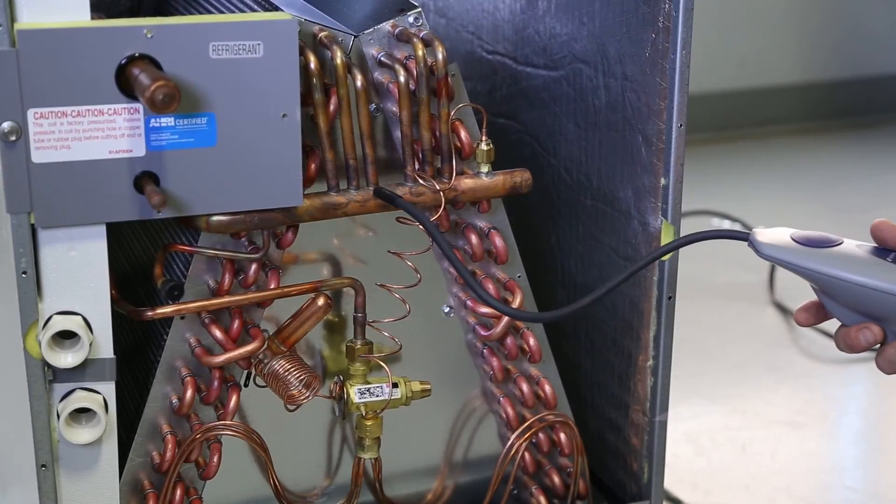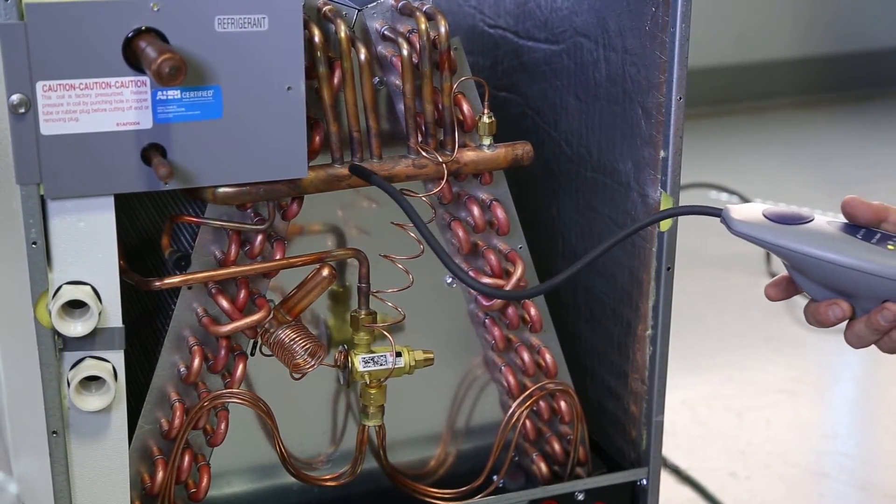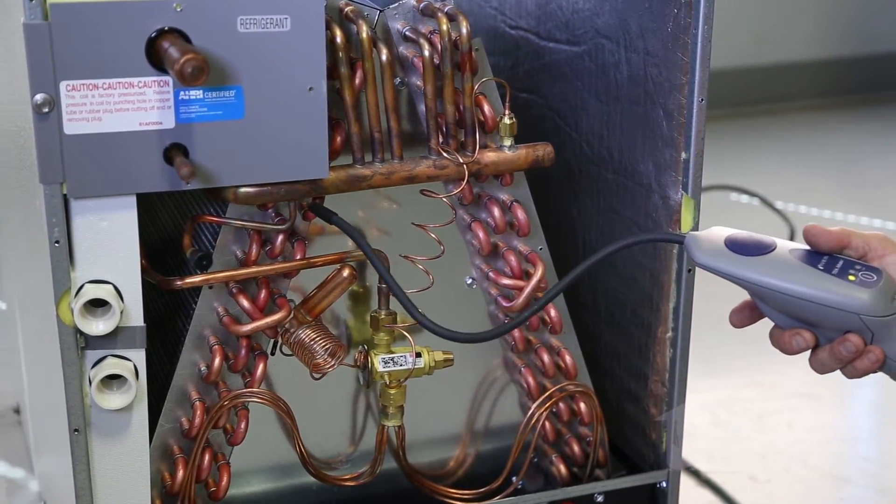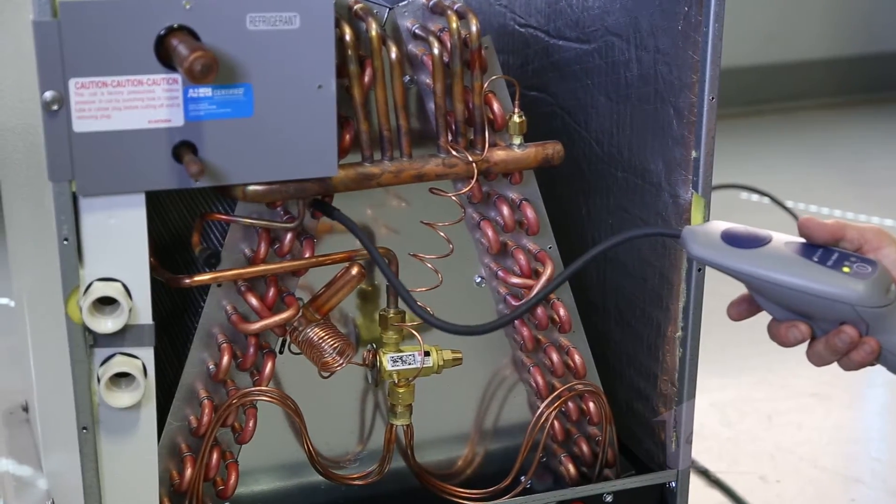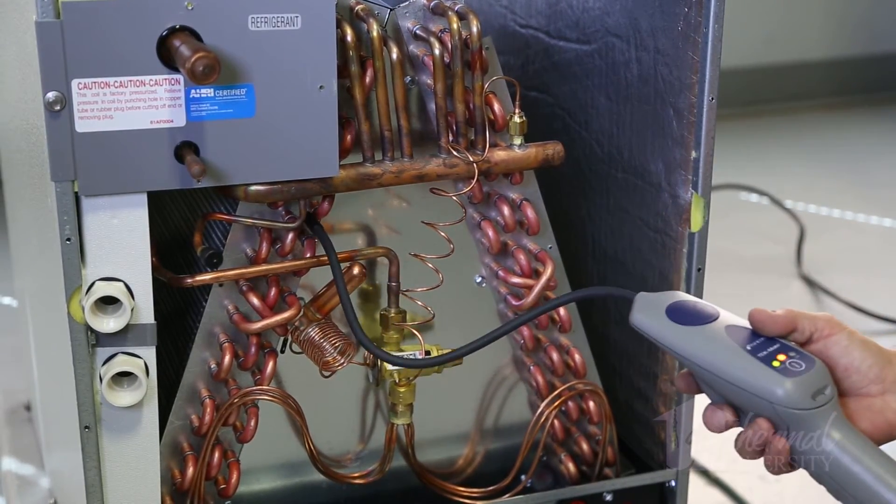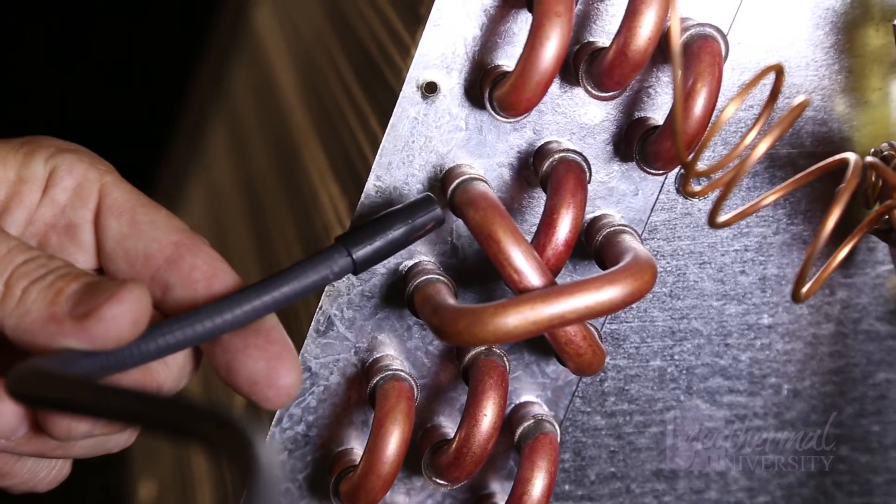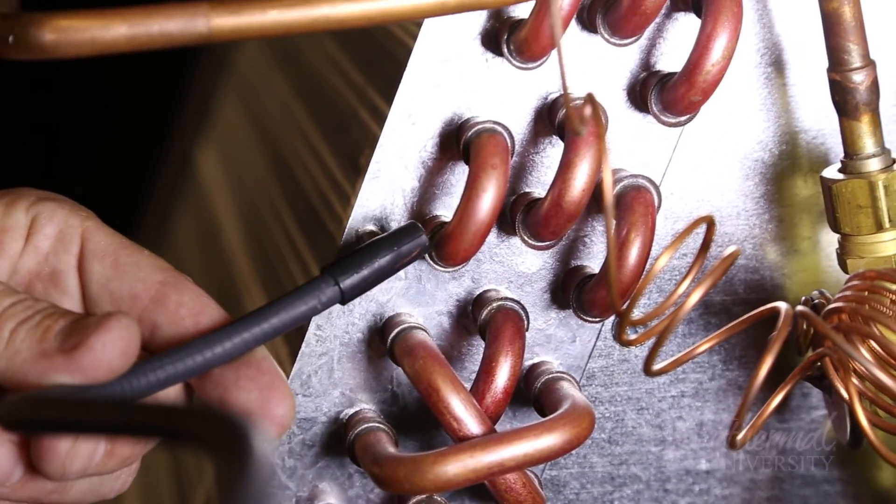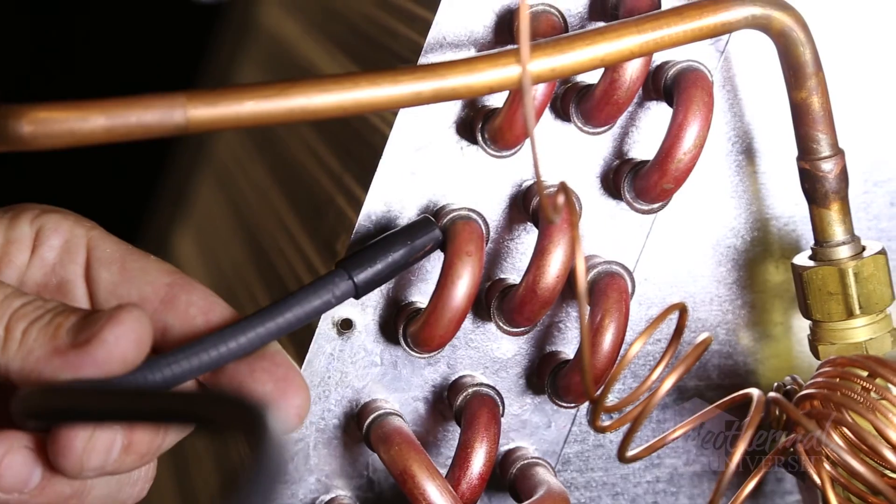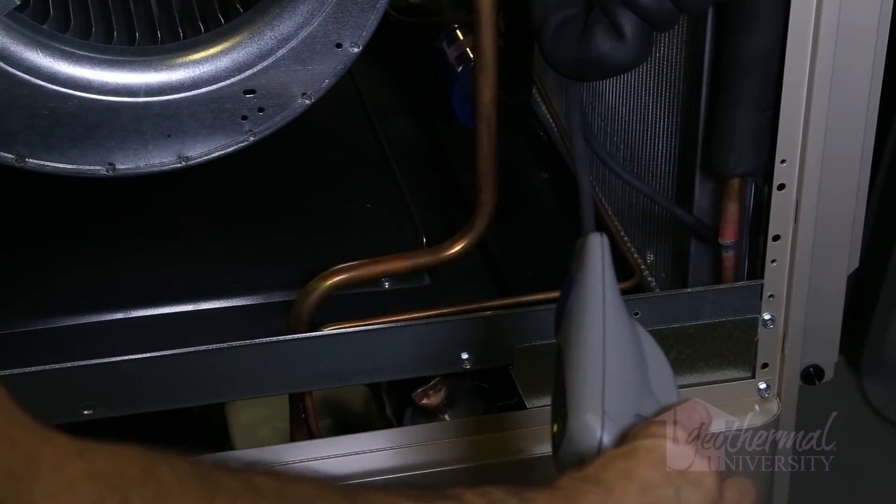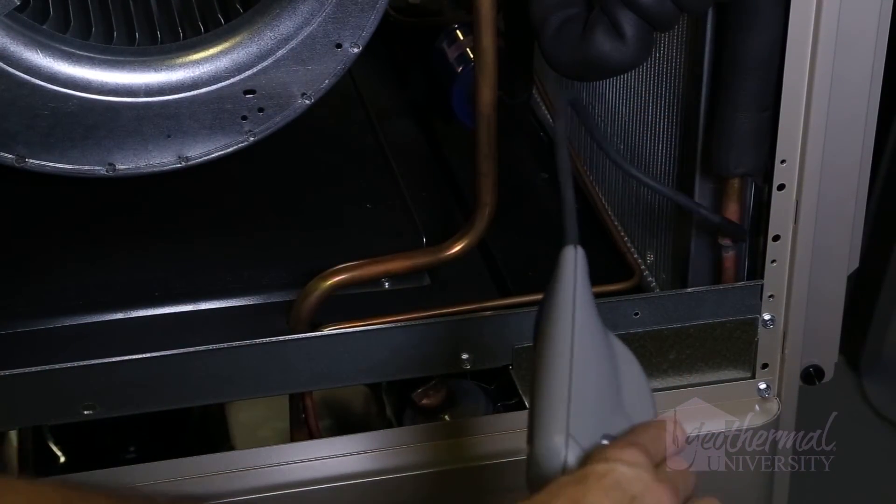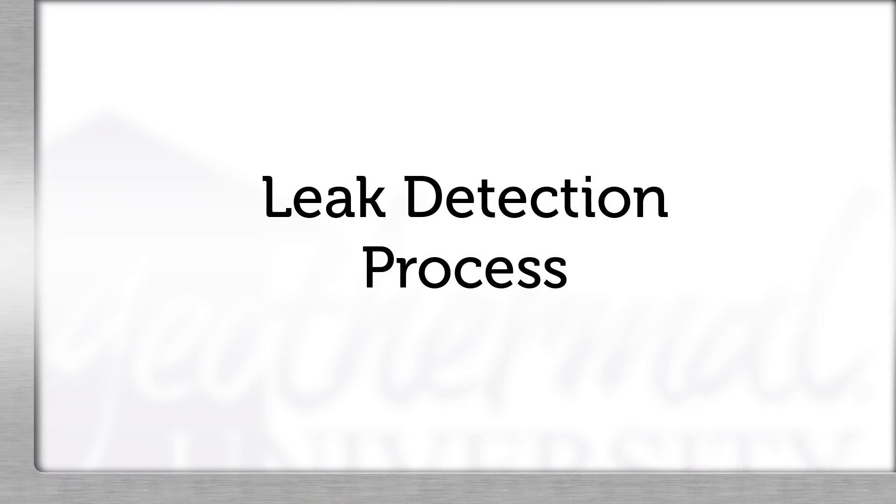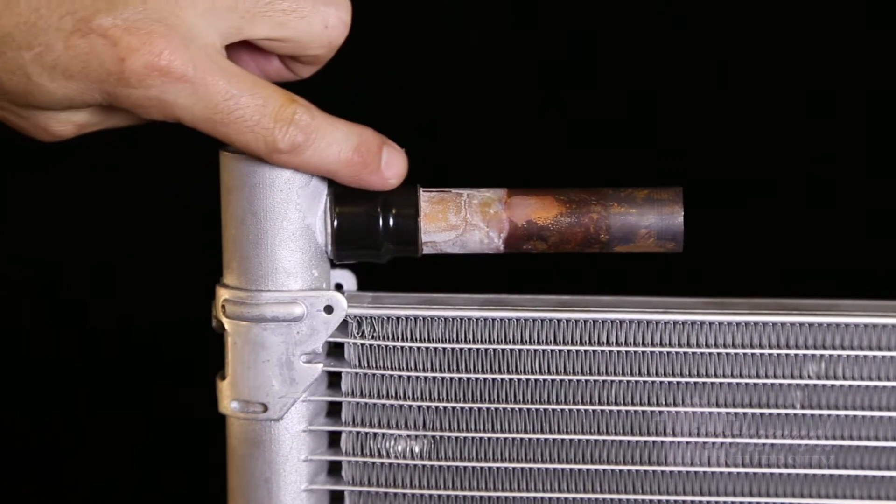For example, you wouldn't expect a leak in a straight section of tubing. A more likely leak would be a braze joint, transition joint, or mechanical fitting. For this reason, you wouldn't typically expect to find a leak in a coil slab. A more likely leak location would be the inlet, outlet, or return bends if equipped. Begin the leak detection process by inspecting all mechanical fittings and braze joints.